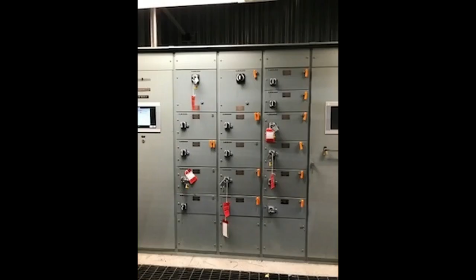I want to talk a bit about work protection, because I know you do this here too — tag out or lockout, whatever phrase you use. One of the most important things operators do is make things safe for maintenance to work on equipment. So it's very important that we lock out, tag out anything a maintainer is going to work on. For example, if we need mechanics to change the seals on that boiler feed pump I showed you earlier, we need to make sure all the electrics are isolated, all the valves are closed in the proper area, the vents are open, the drains are open, and that pump is completely safe for the maintainer to work on, knowing no energy will be introduced into their situation.